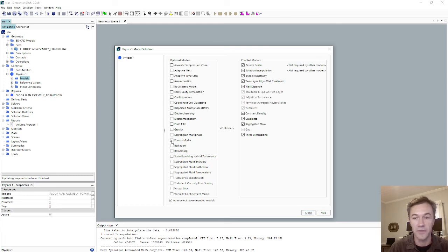It's a property that's convected and diffused and carried with the gas flow in the room. So if we wanted to study the filter as a way to remove a pollutant, we might populate the entire room's volume with a value of 1 of this scalar quantity and watch the reduction, if we assume that the filters have 100% removal efficiency on that.